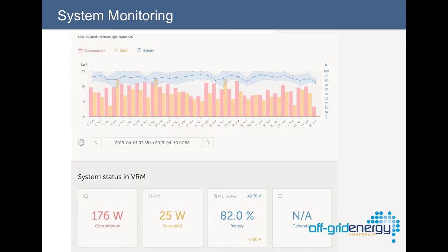You can see here the red line is the consumption per day - I think that's around 10 kilowatt hours. The yellow is the solar production, and the blue line is the battery depth of discharge. In this case, the batteries are really only discharging on average about the top 20% of the battery - I have a feeling this might be a lead acid system we're looking at. You can drill down and see what's happening instantaneously, and if there are problems it comes up with alerts. So if you're looking at getting solar or battery storage, ask about the monitoring system - maybe ask us if you could see an example of it.